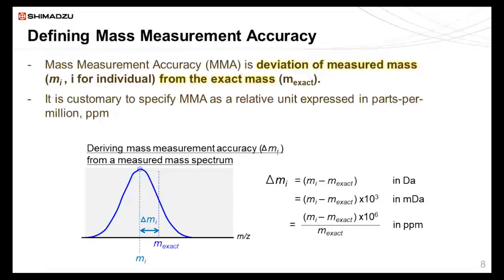On the other hand is the definition of mass measurement accuracy. Mass measurement accuracy, MMA in short, is defined as the deviation of the measured mass from the exact mass, where exact mass means the calculated theoretical mass. M_i denotes the individual mass measurement, whereas M_exact is the theoretical exact mass. And it is customary to specify MMA as a relative unit expressed in parts per million, ppm.